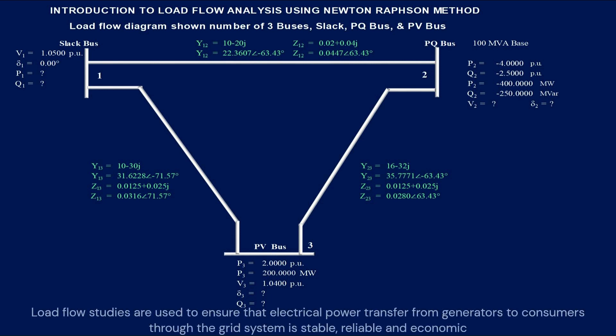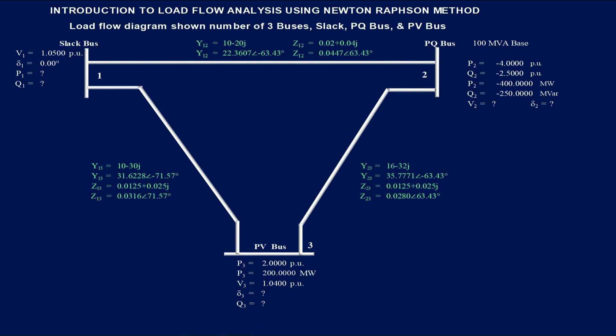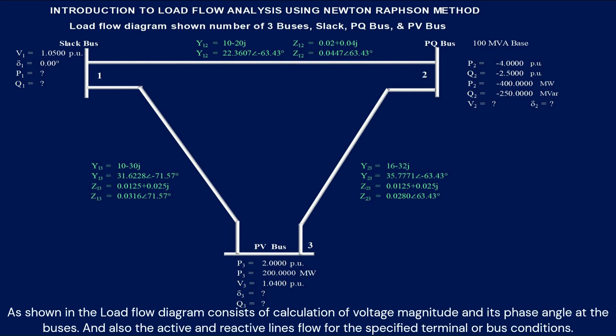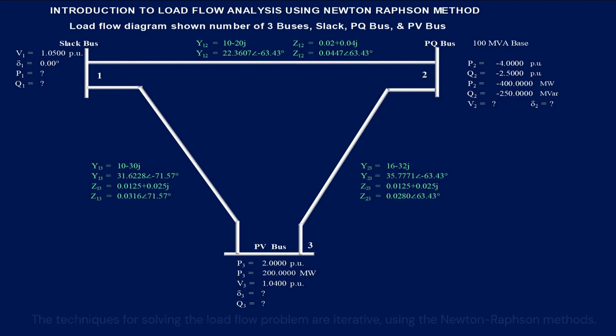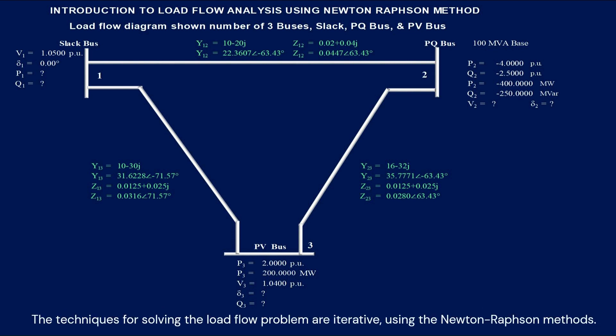Load flow studies are used to ensure that electrical power transfer from generators to consumers through the grid system is stable, reliable, and economic. As shown in the load flow diagram, it consists of calculation of voltage magnitude and its phase angle at the buses, and also the active and reactive power line flows for the specified terminal or bus conditions. The technique for solving the load flow problems is iterative using the Newton-Raphson method.